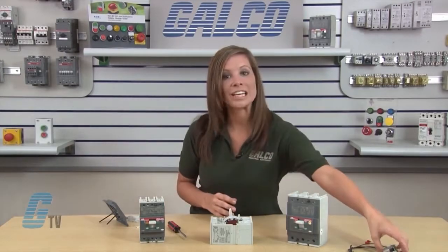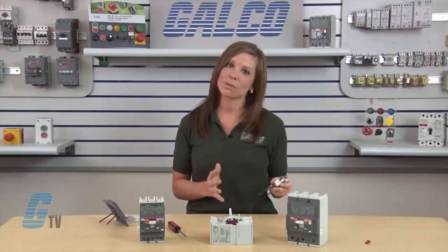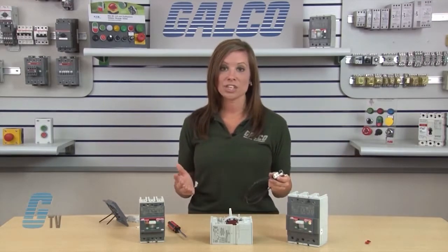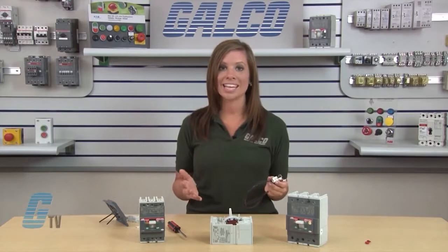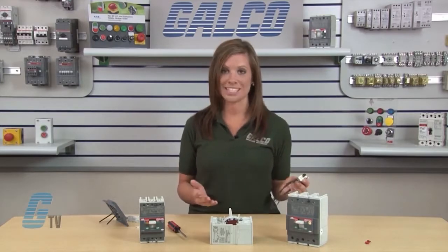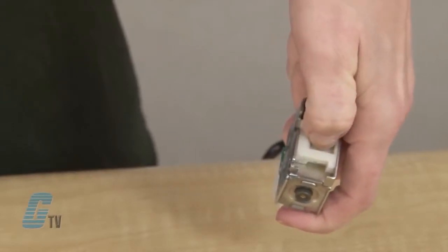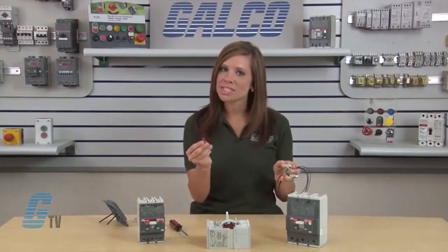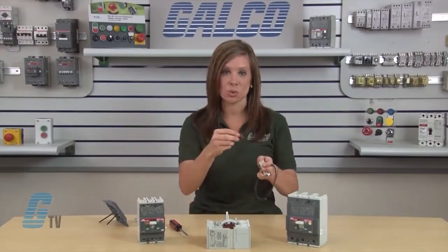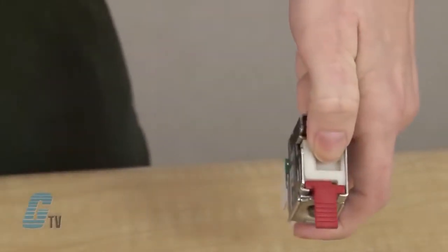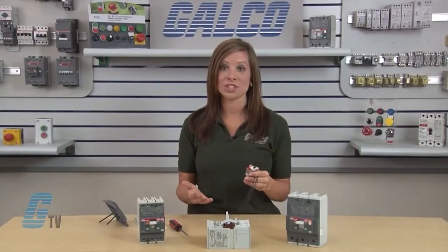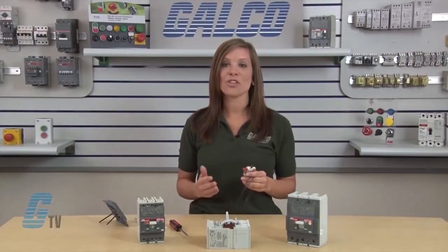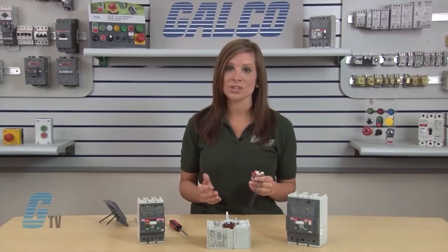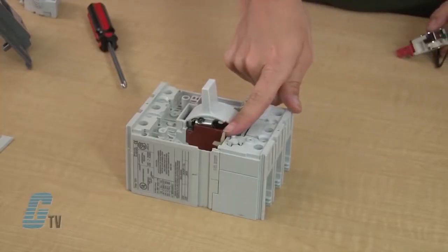Now, before installing the UVR unit, it will need to be preset, meaning that the spring action of the mechanism will have to be held back into position to allow for proper installation. I'll accomplish this by holding down the mechanism in the UVR with my thumb while holding it in one hand. With my other hand, I will temporarily install the installation tool like this, which will hold the UVR mechanism in proper position for installation.